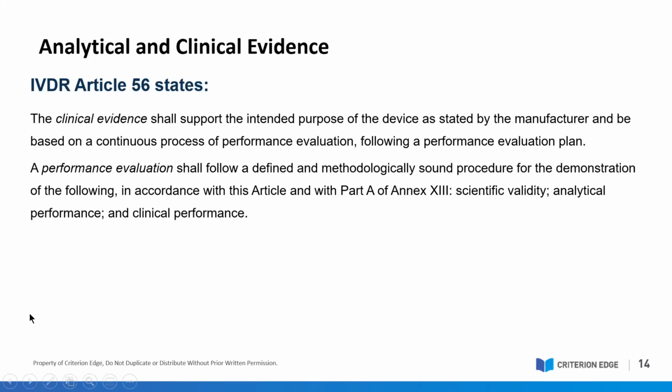The clinical performance will include things such as diagnostic sensitivity or diagnostic specificity. So they're both sensitivity and specificity definitions, but they have clearly different purposes. This type of data may also include positive predictive value or negative predictive values, likelihood ratios, or expected values in a normal versus an infected population.